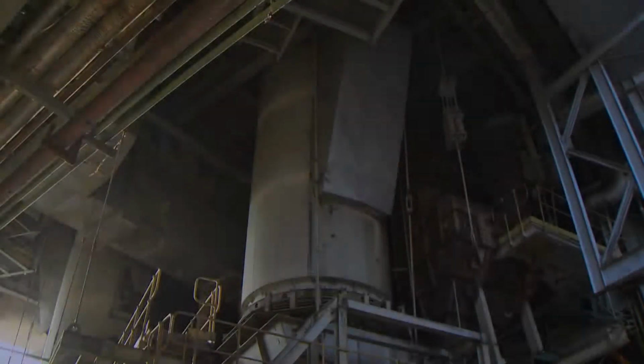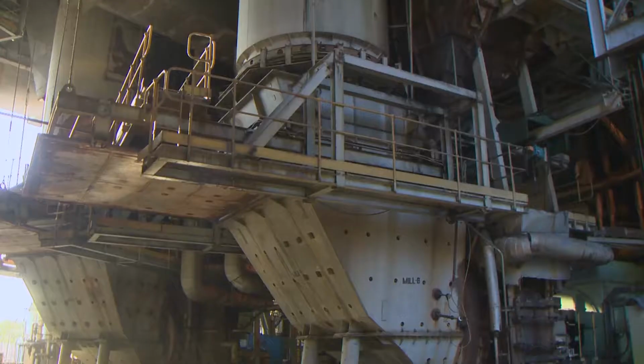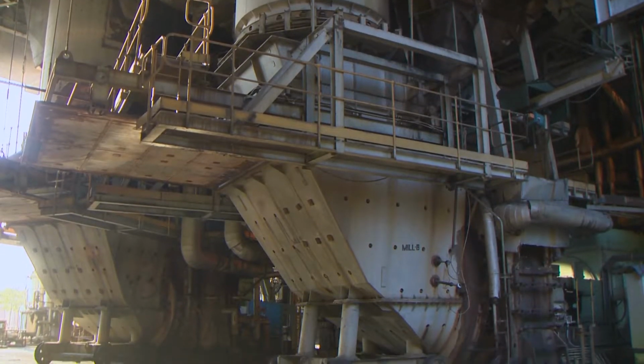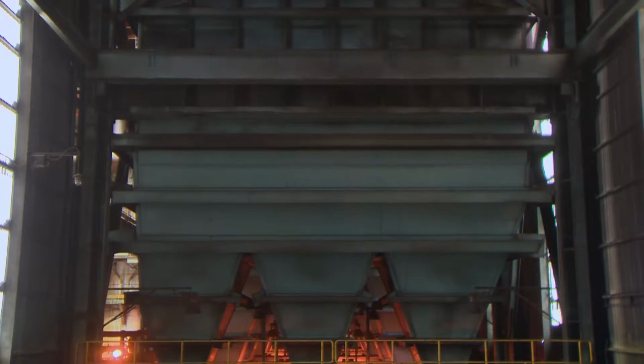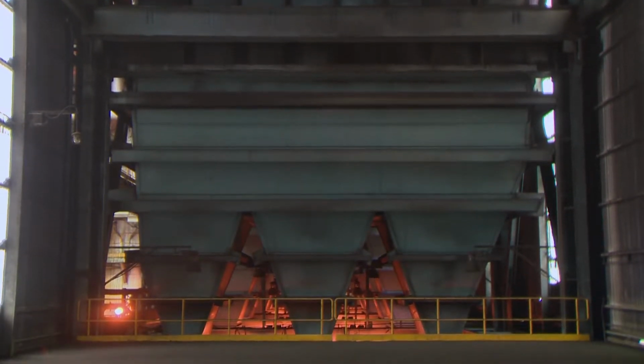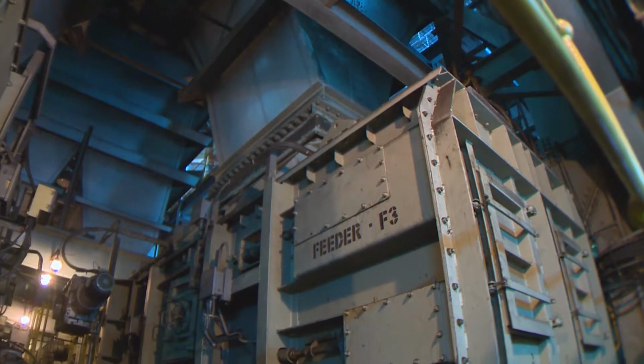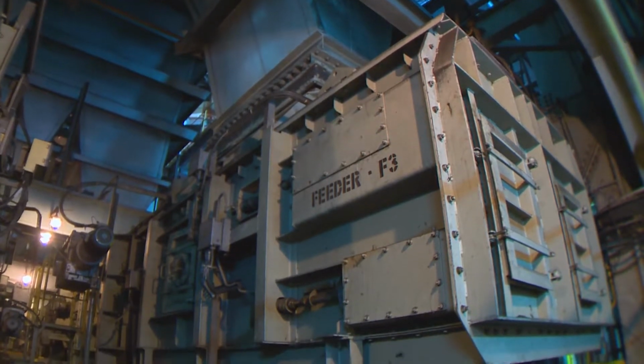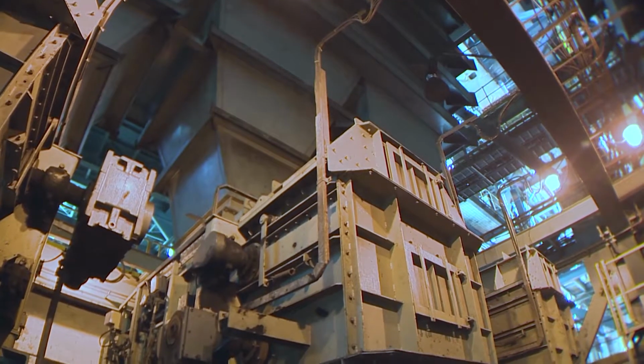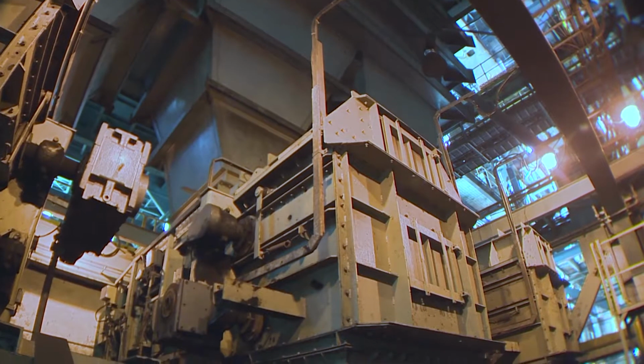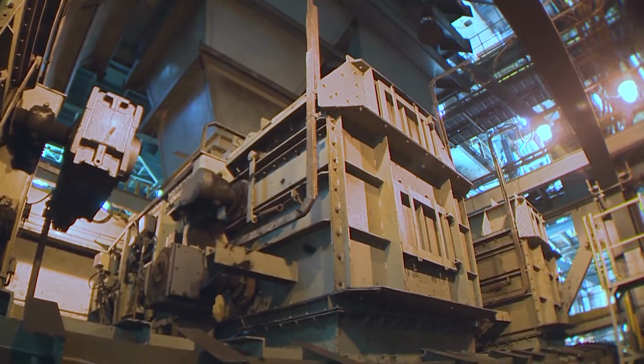Firing system. Tangential suspension firing system is adopted in these boilers. The lignite stored in the boiler bunkers is transported to the belt conveyor by plate belt feeder. The lignite quantity can be varied by adjusting variable frequency drive motors.